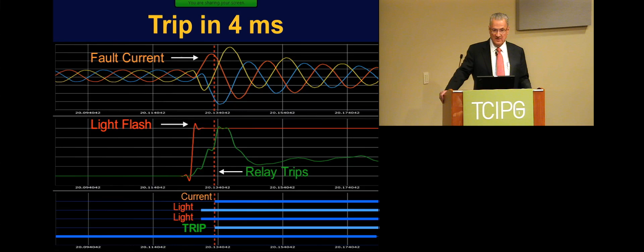What was security like when we did our first relay in 1984? First of all, we had 2 access levels. Now think back, 1984 meant 300 baud, maybe 1200 baud, but even 300 baud beat making a trip out to a substation even 30 miles away if you wanted to find out what happened. And we were very interested in delivering that capability to people because we could tell them where the faults are. One trip in a helicopter to patrol a line equaled the cost of one of these instruments at that time. That's how quick the payback is.